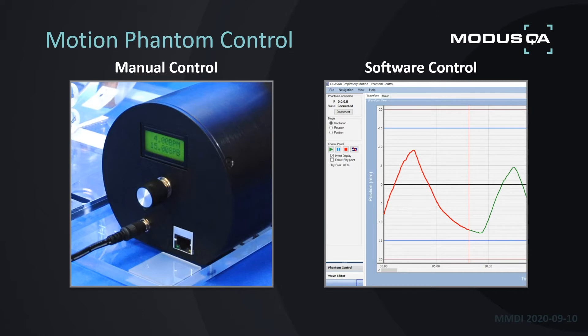This is only available on the CT-based Phantoms, but with those Phantoms you also have the option of connecting to our software suite, which allows you to import waveforms from an SGRT system and replay those waveforms on the actual Phantoms. You can connect directly with an Ethernet cable to your laptop, or connect through a local area network.